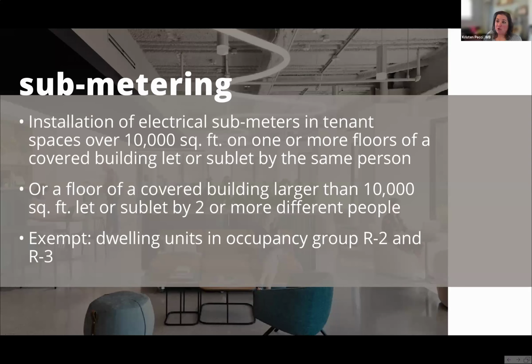So the next section of Local Law 88 that applies is the section on tenant electrical submetering. This dictates the installation of electrical submeters within tenant spaces either over 10,000 square feet on one or more floors of a building, let or sublet by the same person, or a floor of a building larger than 10,000 square feet, which is let or sublet by two or more different people.